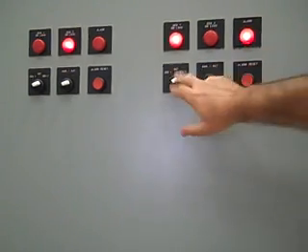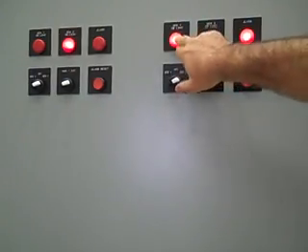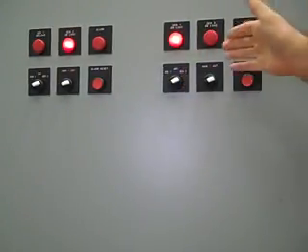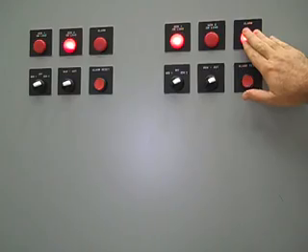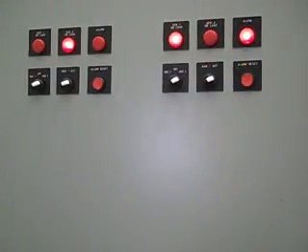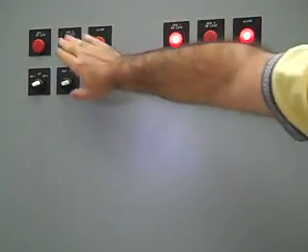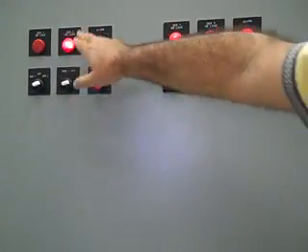We have an alarm again because we had generator 3 selected. We can see that we're in generator 1. So the only situation that happened is Gen 3 failed. That's why we have an alarm here. But it went ahead and transferred to generator 1. Generator 2 is still running, still good.